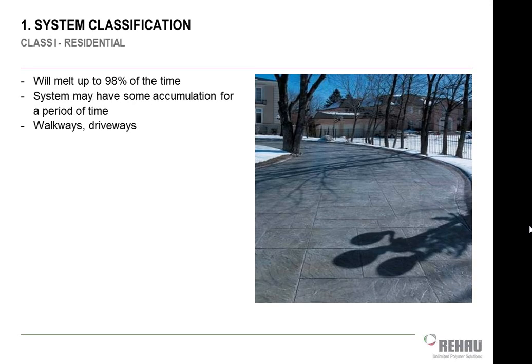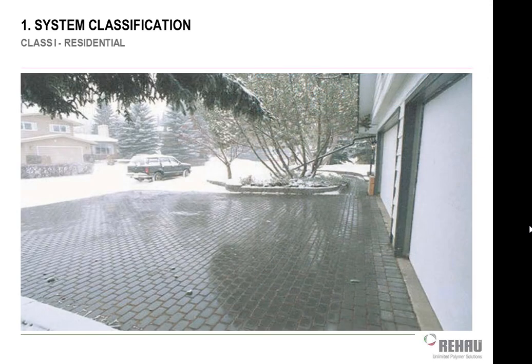So the class 1 is what we typically use residentially. It's basically going to take care of 98% of your snowfall issues. Yeah, there's going to be times when there's just a ton of snowfall and it won't be able to keep up, but usually we're not going to design it for that because the system's going to be twice as big as it needs to be, and we don't really want to do that. You can have some accumulation for a little bit of period of time, so it may take a little bit longer to melt the snow off because the system is going to be a little bit smaller.